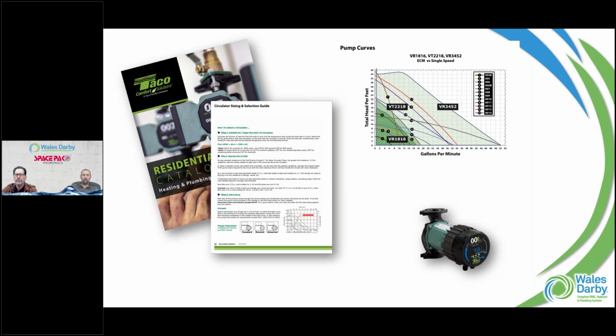We just did this with a guy, two 0011s. So we doubled our head. We did it in series, 8 to 10 inches between circulator to circulator. You don't want to bolt the flanges together. But now, if a 0011 goes down, it's a lot easier to find a 0011 than it might be to find a VR circulator. So there are some design considerations there, but this book is a huge tool for us. What were we, two or three years, probably even a little bit more since Taco came out with this? The book? Yeah, it's like the third revision because I keep adding new stuff.